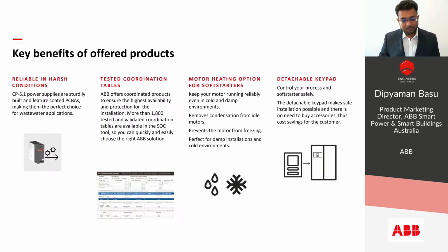When it comes to a motor heating option, our soft starters have a special option which can be programmed in the pre-start of a motor. What the soft starter does is pass a small DC current through the motor, enough to generate heat to allow removal of any condensation in damp and wet environments. This does not start the motor. It's just to allow the condensation to go away, and this is an ideal option for wet and damp environments. And then we have the detachable keyboard, making installation easy and also saving costs on additional accessories.